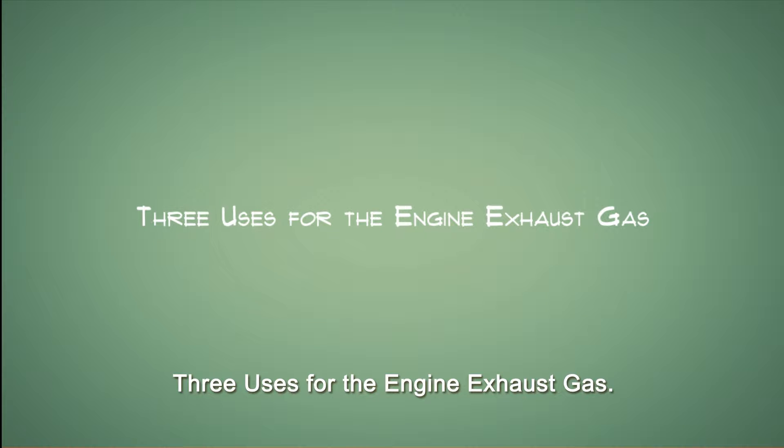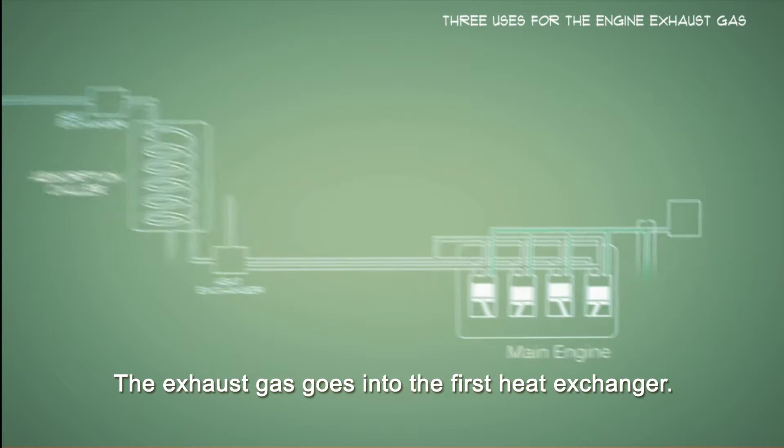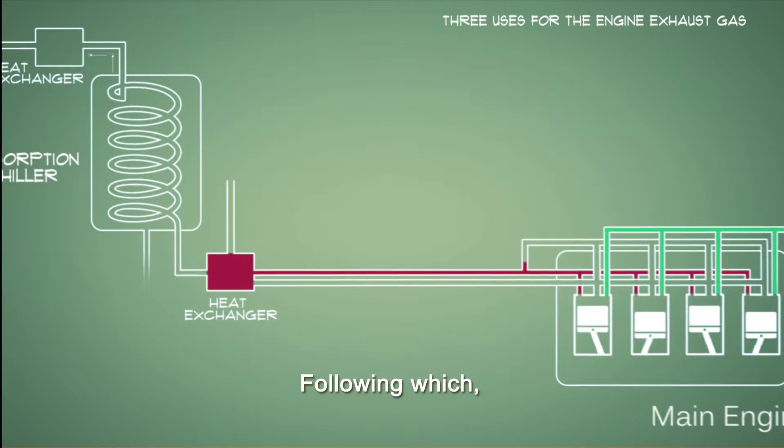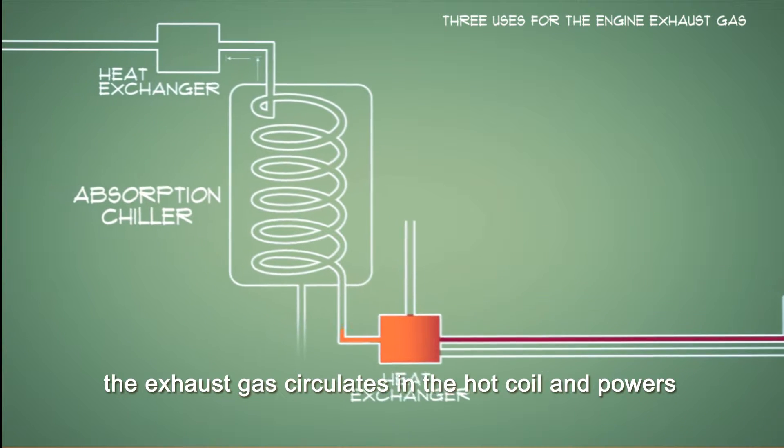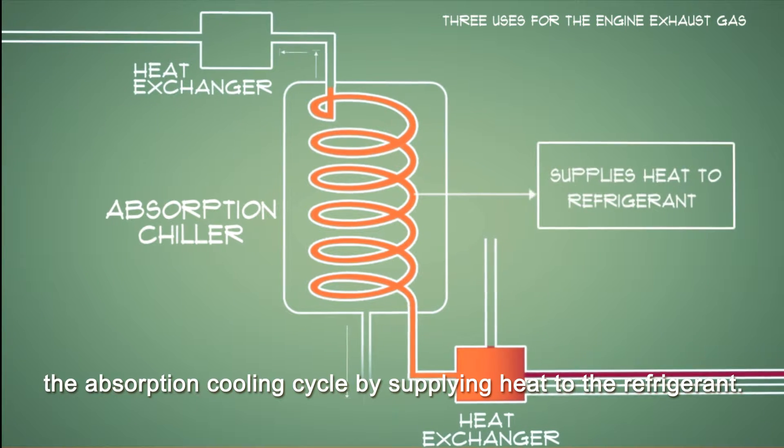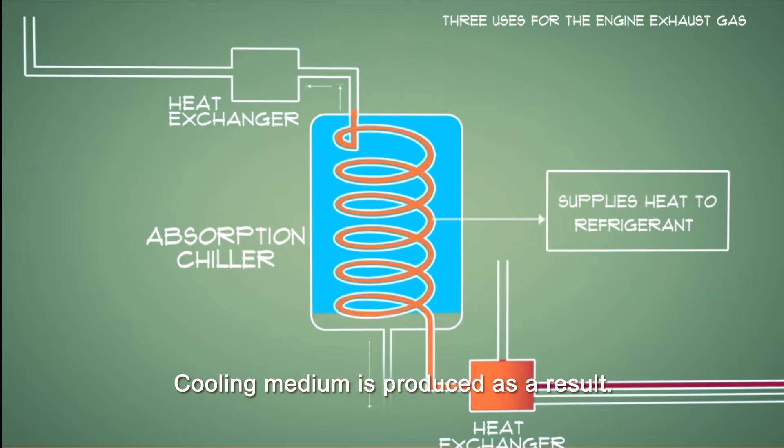Three uses for the engine exhaust gas. Firstly, engine exhaust to power absorption chiller. The exhaust gas goes into the first heat exchanger. Following which, the exhaust gas circulates in the hot coil and powers the absorption cooling cycle by supplying heat to the refrigerant. Cooling medium is produced as a result.